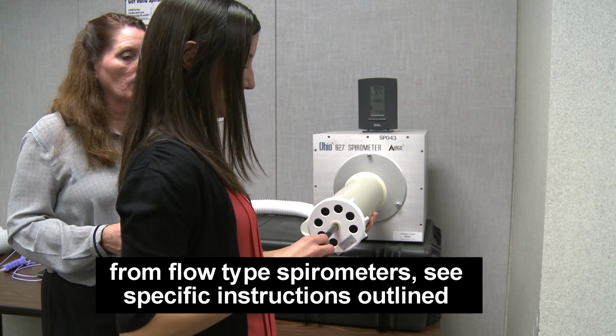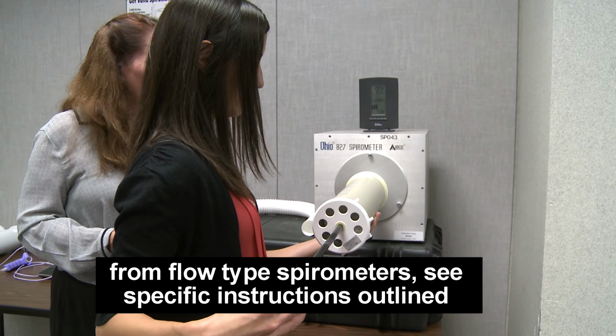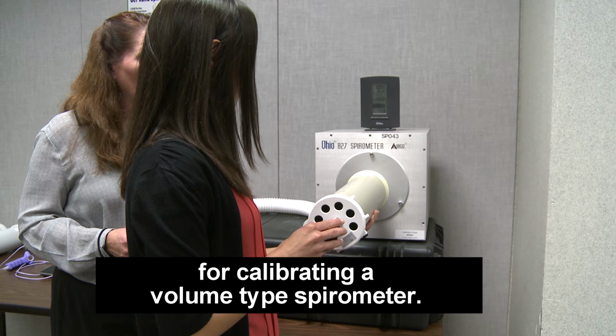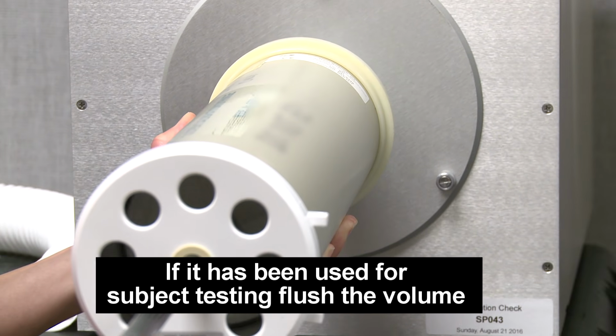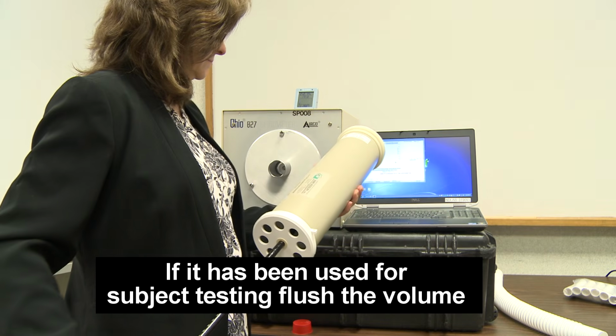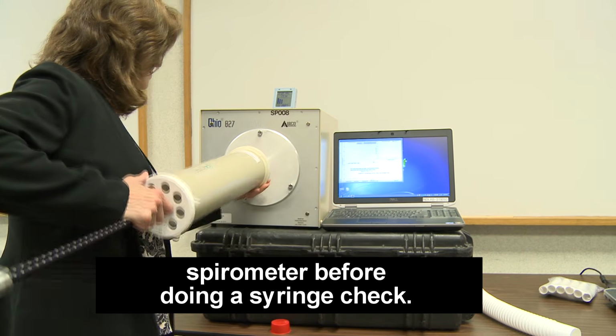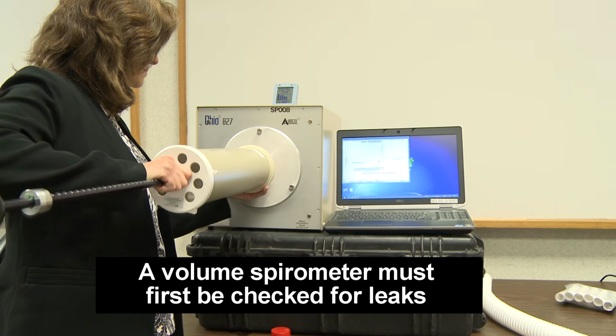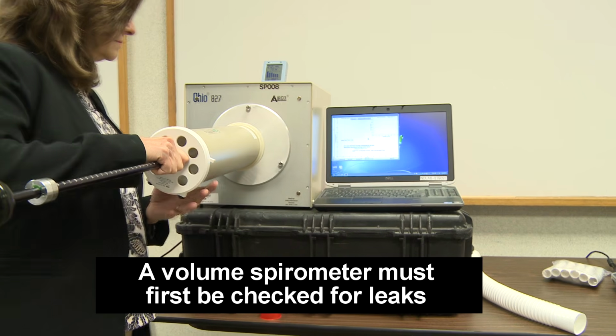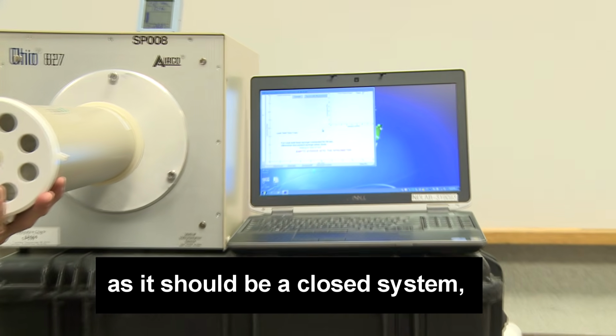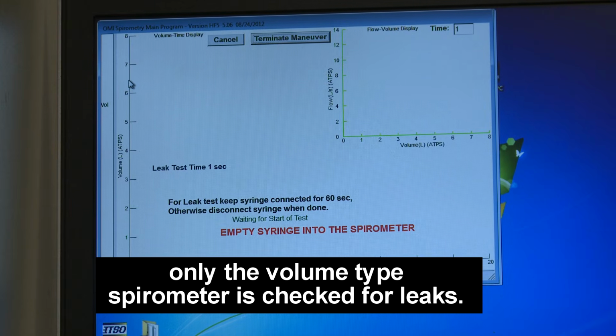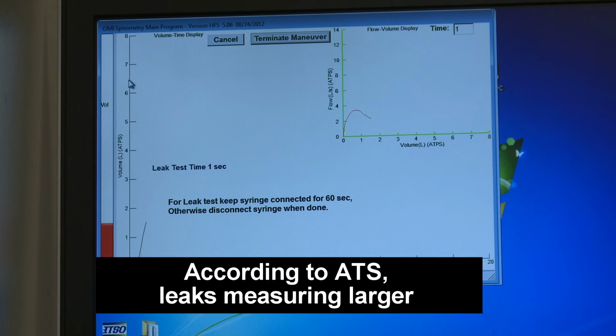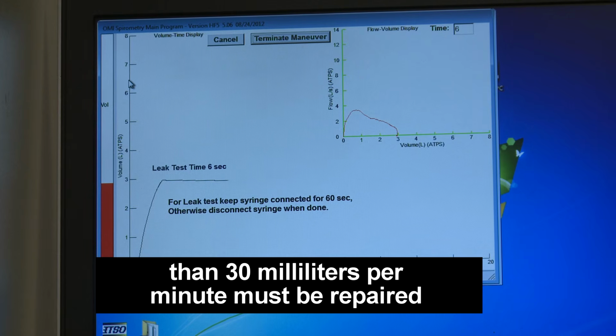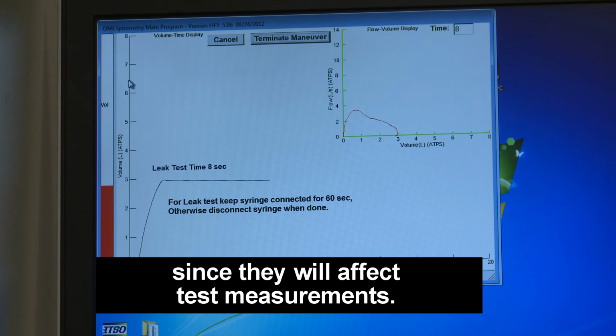Volume spirometers are a little different from flow-type spirometers. See specific instructions outlined in the user's guide for calibrating a volume-type spirometer. If it has been used for subject testing, flush the volume spirometer before doing a syringe check. A volume spirometer must first be checked for leaks, as it should be a closed system. Only the volume-type spirometer is checked for leaks. According to ATS, leaks measuring larger than 30 milliliters per minute must be repaired, since they will affect test measurements.